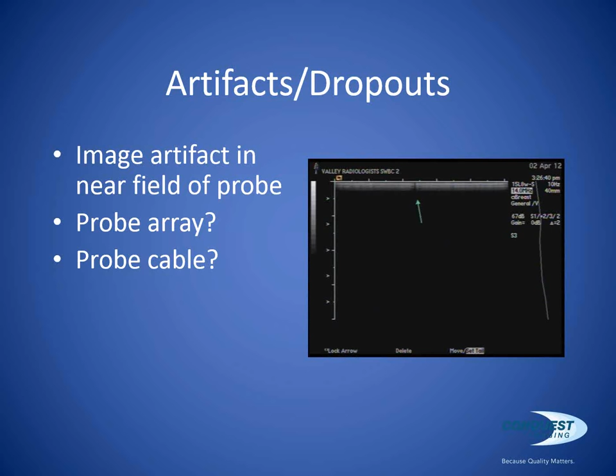You do not want to use any object that is sharp because the lens of a probe is very delicate. So you want to use something that is rounded. A screwdriver works well, not the tip, but the shaft itself if it's round. But you can actually slowly move that metallic object across the face of a transducer, and it'll create a very bright beam within the image. If that beam fluctuates as you're moving it across, that will tell you that you either have a weak element, a dead element, or perhaps a bad cable.